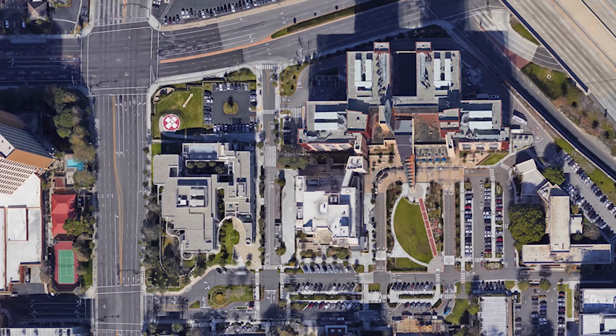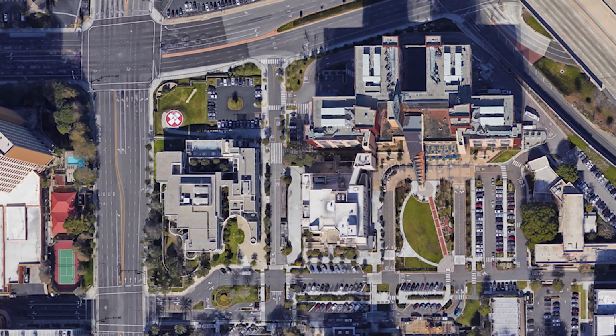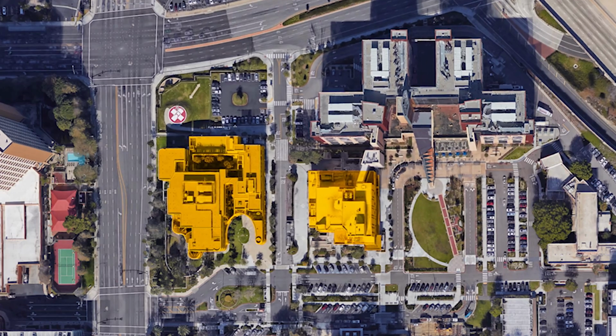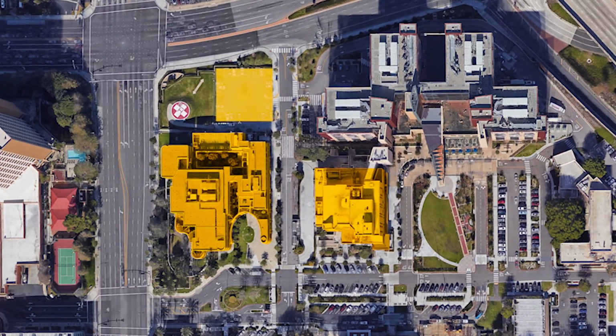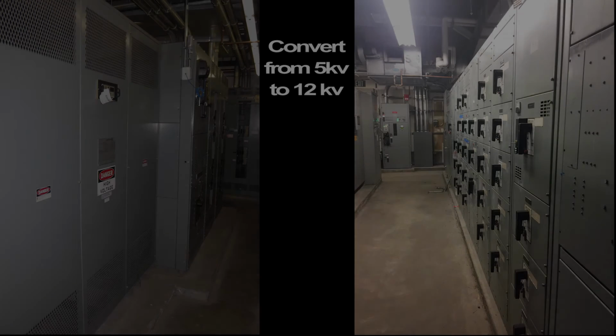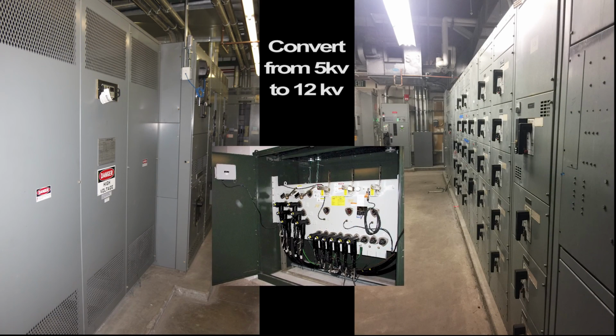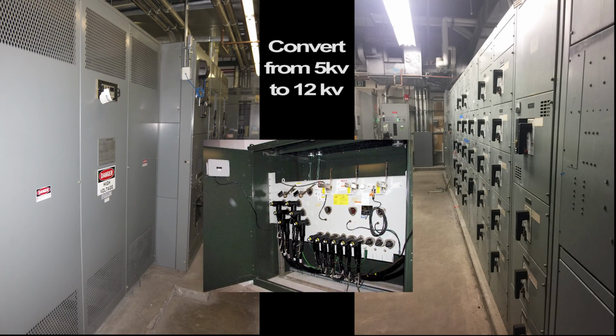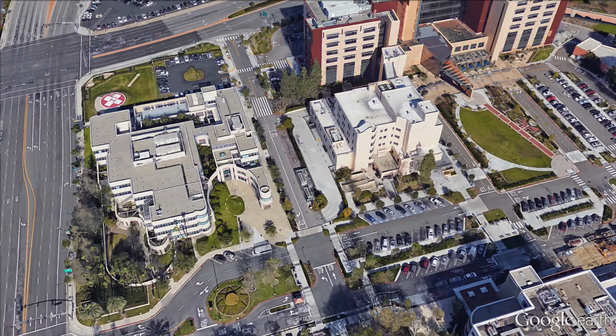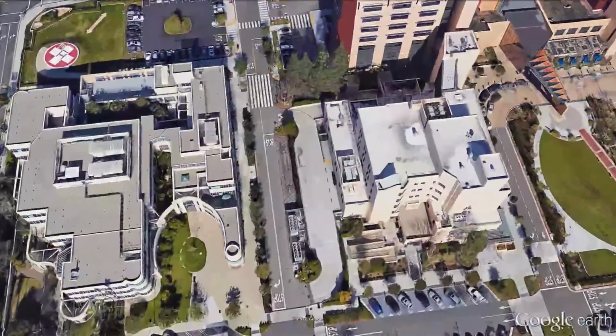The design also frees up space on the north side of the yard for future electrical and mechanical equipment by removing the existing modular chiller plant and associated cooling towers. This could be used for a future 6th emergency generator on the north side of the yard. The chilled water connections to buildings 1A, 3, and the future emergency department expansion building and conversion of existing 5 kV normal and emergency systems to 12 kV system are an important element of the project. We've carefully sequenced and phased these activities to minimize interruptions to the campus.